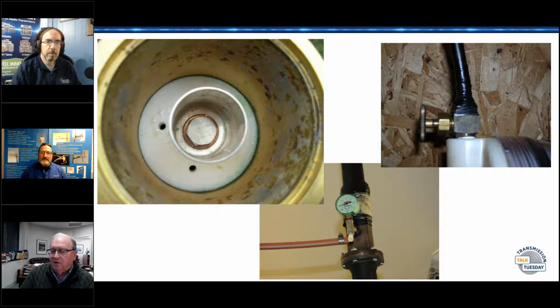The other thing is using different gases. Old TV lines, we would use Freon, basically, not to cool it, but because it had a different voltage withstand ratio. There was also another freon-like chemical we used, and if it burned in the presence of Teflon, it would make phosgene gas, which was a bad thing. But there are lots of tricks for pressurizing line.